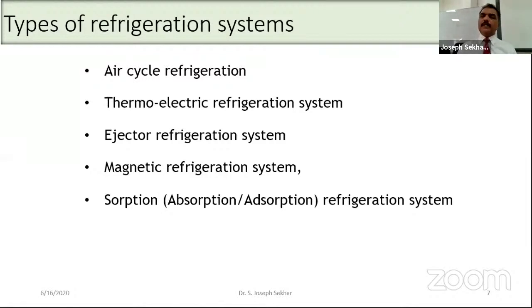The main issue behind this technology is that it cannot be used for very low temperature. Maybe if you go for a temperature of 4 degrees or 3 degrees, this will be good, but if you go for -10, -20, absorption may not work. The second issue is we cannot go for small systems - we have to go for at least a 50 TR system. Only then is this absorption type of refrigeration possible.